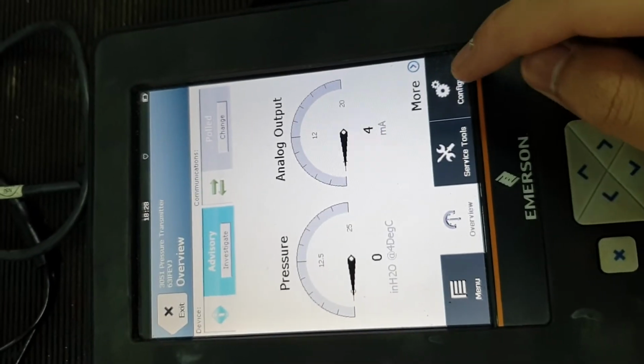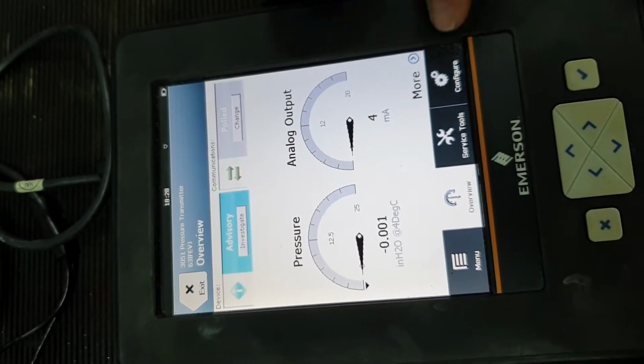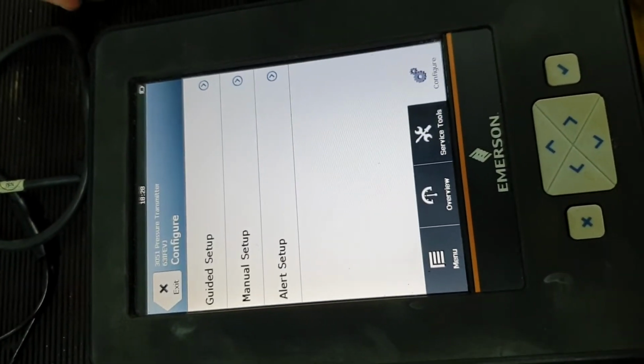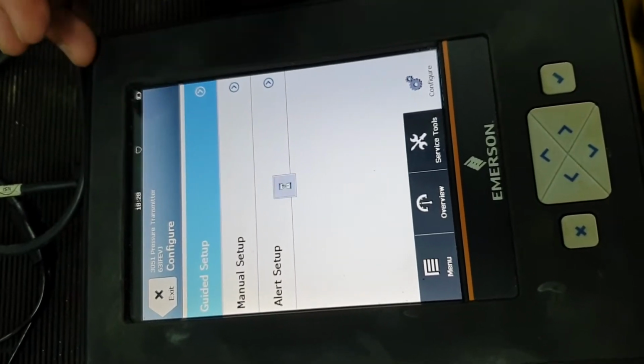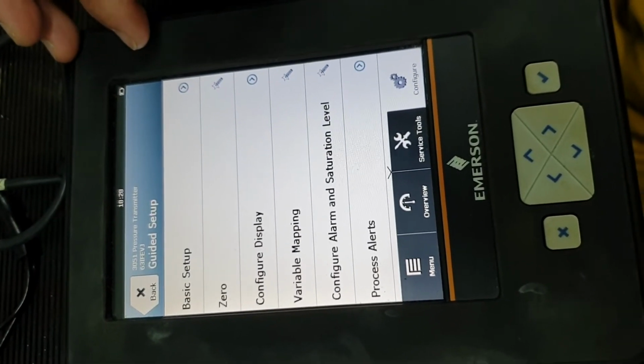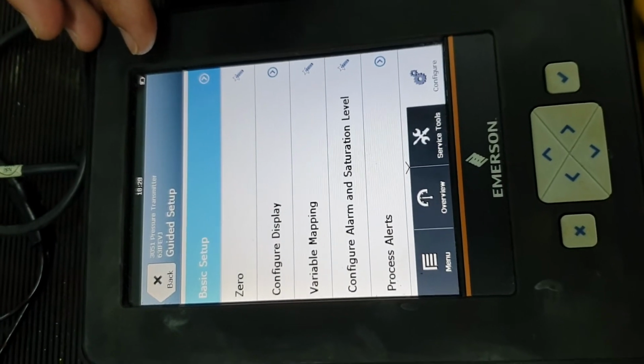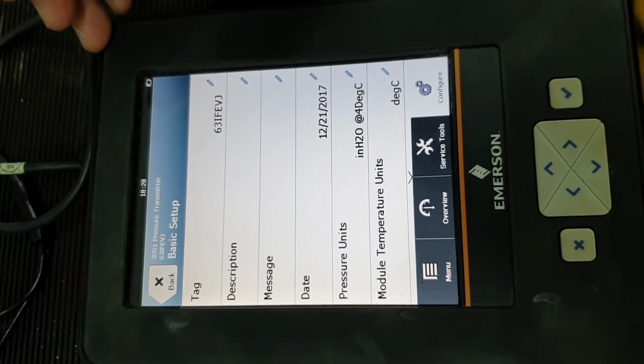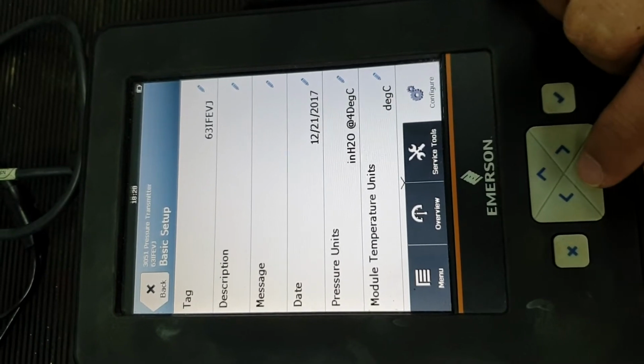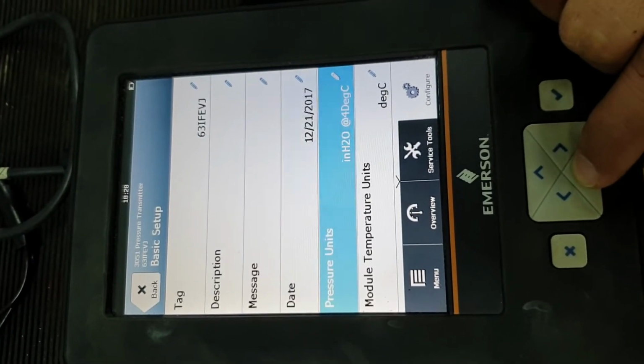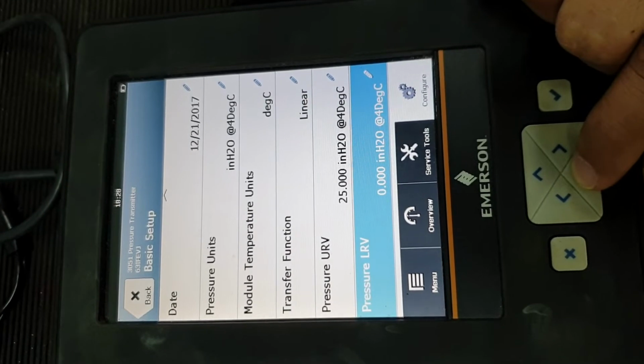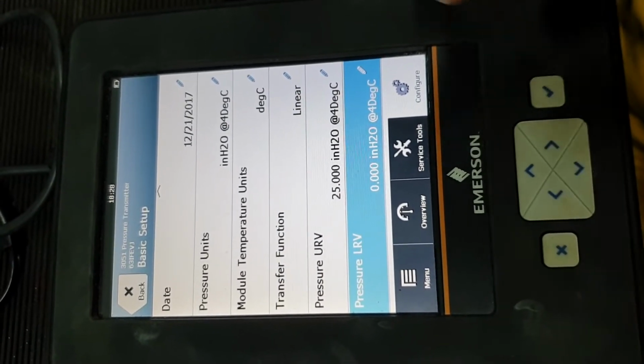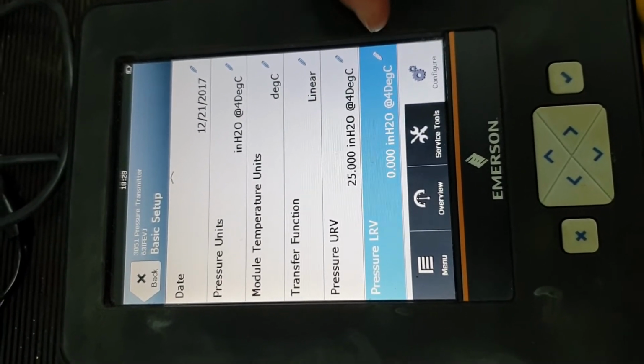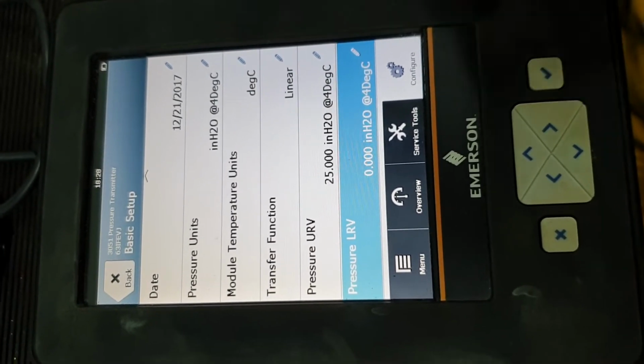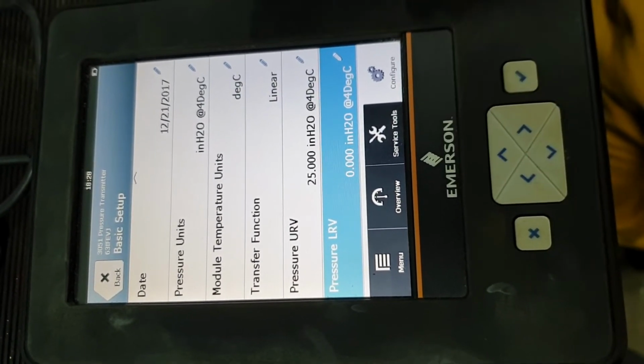To ensure that our reading is within the scale, we will go to the configure side, and then we will go to guided. Next we go into basic setup, and then we proceed to the range of scales, which is 0 to 25, which can be selected at the pressure LRV and the pressure URV, the lower and the upper range value. Once we have selected that, we go back to our overview.